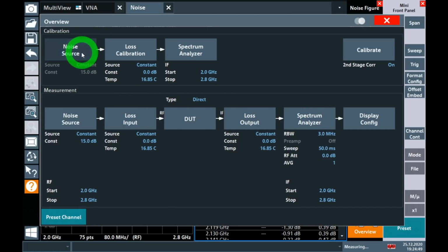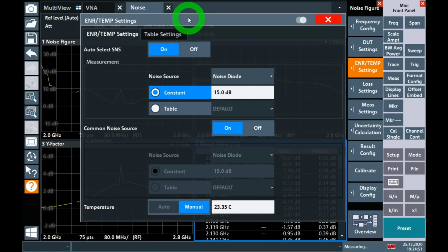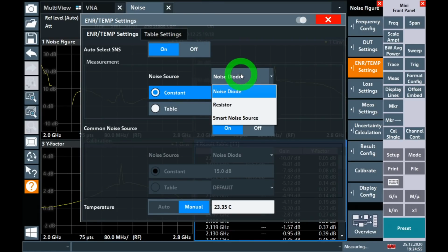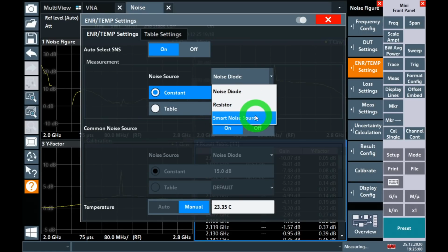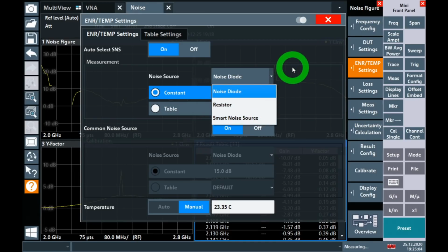But the nice thing is if you go under noise source here, because we do have the 28 volt drive, you can mention what kind of noise source you have, whether it's a noise diode or resistor. But if you go under smart noise source here, then you will basically have all the calibration coefficients automatically downloaded into the ZNL if you have that kind of a noise source, just the same way that the power sensor would work, download everything into the instrument.